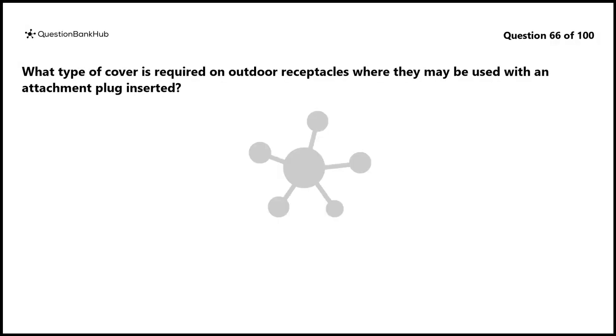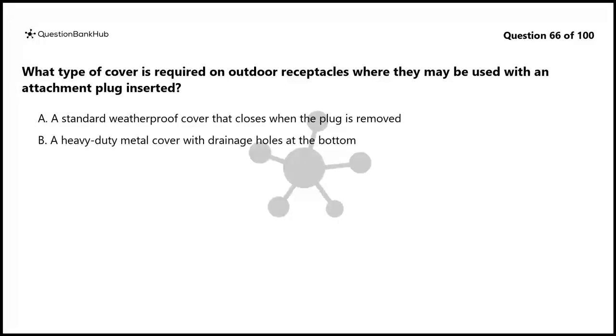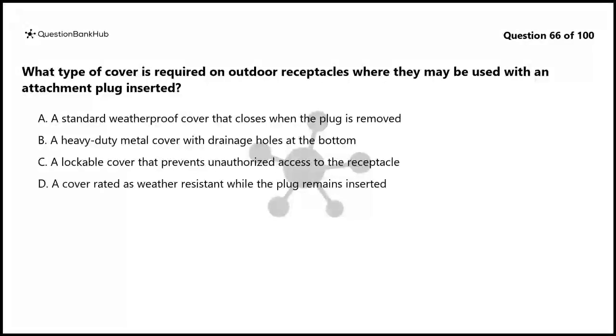Question 66. What type of cover is required on outdoor receptacles where they may be used with an attachment plug inserted? A. A standard weatherproof cover that closes when the plug is removed. B. A heavy-duty metal cover with drainage holes at the bottom. C. A lockable cover that prevents unauthorized access to the receptacle. D. A cover rated as weather-resistant while the plug remains inserted.